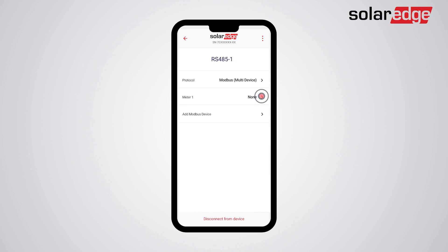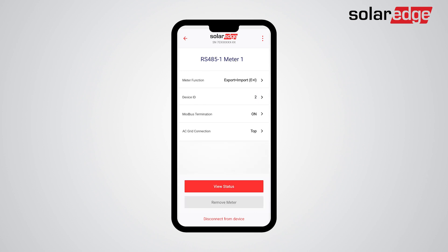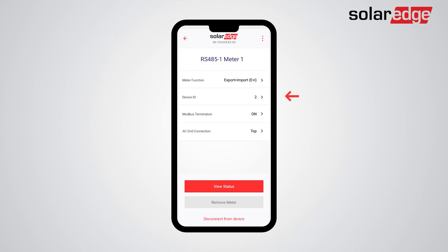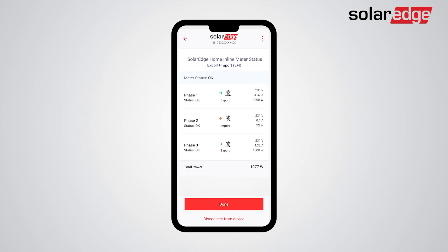Tap Meter 1 to start configuration. In case you need to change configuration parameters, use the arrows on the right-hand side and the drop-down menu to configure. Note that meter function and AC grid connection should reflect the physical wiring and position of the meter in the electrical cabinet. Device ID should reflect the meter ID which is set through the inline meter display settings. Now tap View Status.